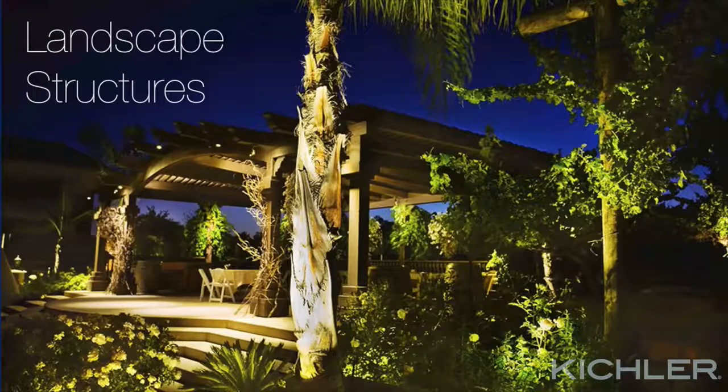When choosing fixtures for downlighting, make sure you don't overdo the amount of light on the ground. A 180 lumen 60-degree fixture, a 16005, will put about 1.7 foot candles onto the ground from a height of 8 feet. Unless this is a high activity area, you probably don't want much more light than that.